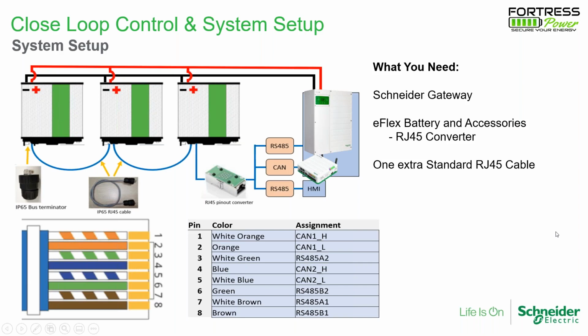The way you communicate with the Schneider system over RJ45 is through pinouts 7 and 8. Depending on the standard you use, the color might differ, but it's always the last 2 wires, 7 and 8. You strip those off and connect to the Schneider Gateway, then go into the gateway to set up the system - I have another slide showing a bit of that interface.